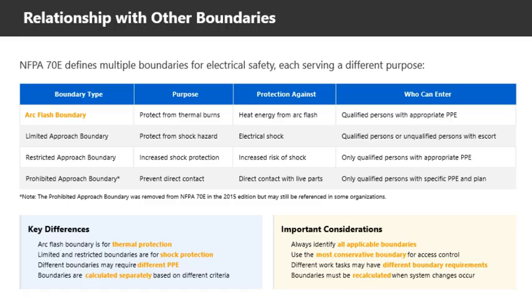The key differences to remember are, the arc flash boundary is for thermal protection, while limited and restricted boundaries are for shock protection. Different boundaries may require different types of PPE. The boundaries are calculated separately based on different criteria, and may result in different distances from the same equipment. Important considerations include always identifying all applicable boundaries for your work, using the most conservative boundary for access control when multiple boundaries apply, recognizing that different work tasks may have different boundary requirements, and understanding that boundaries must be recalculated when system changes occur. Don't assume that one boundary covers all hazards. You need to consider both arc flash and shock protection boundaries for comprehensive safety.